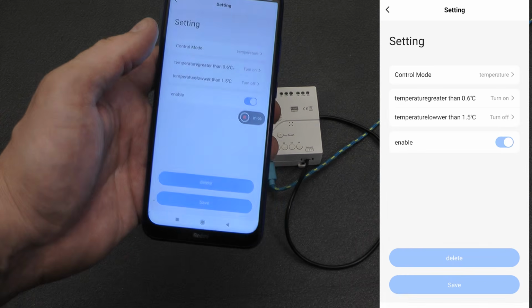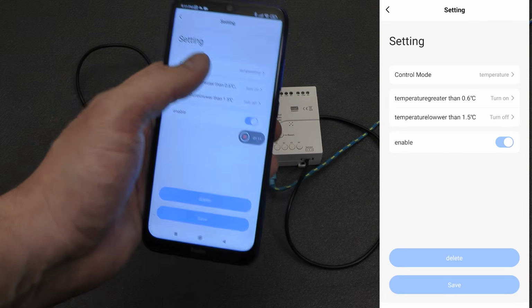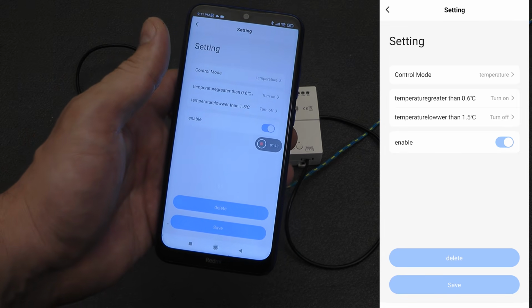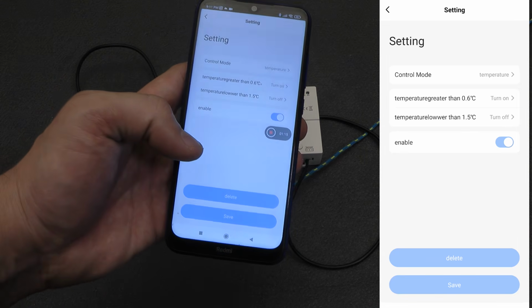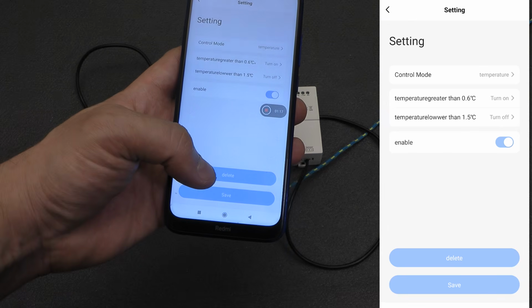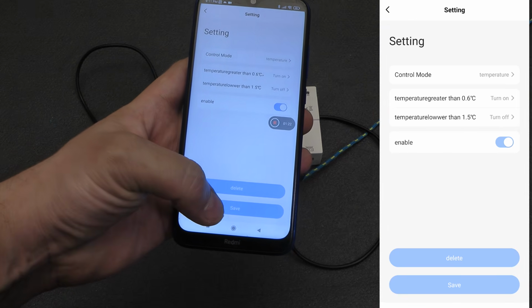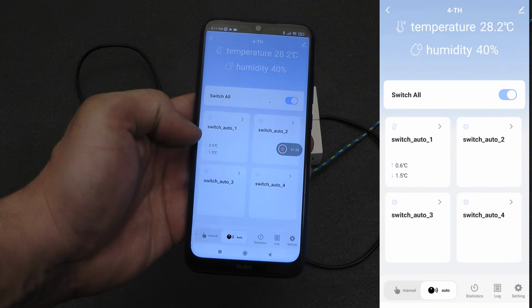The temperature is set with a step of 0.1 degrees, and the humidity with a step of 1%. For example, you can create simple thermostat logic. If the temperature is below the set value, turn the relay on, and if it is above another value, turn it off. After setting it up, do not forget to enable this scenario and save it.